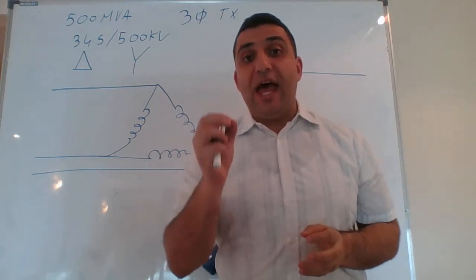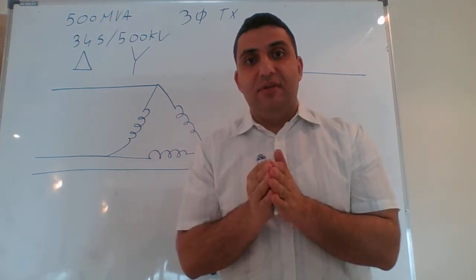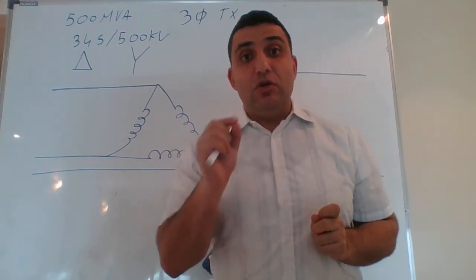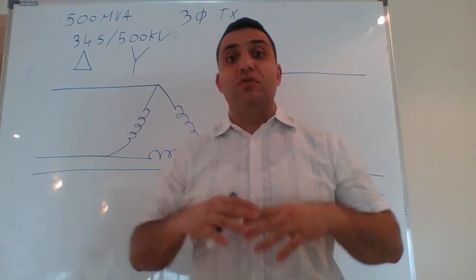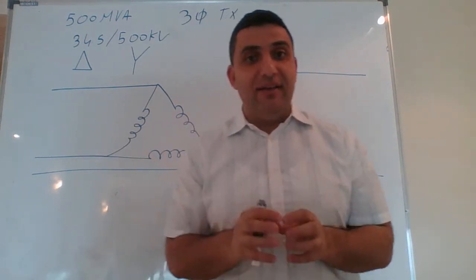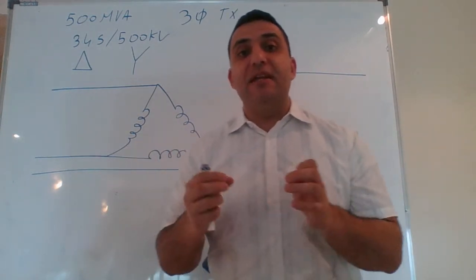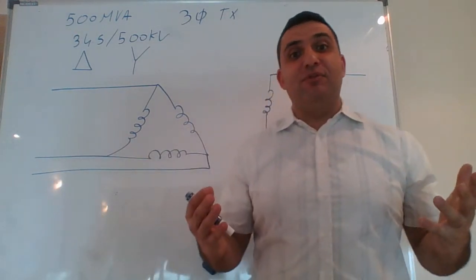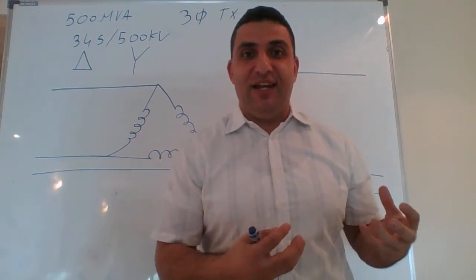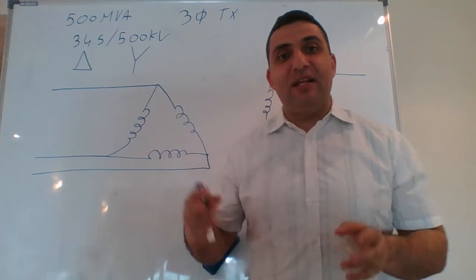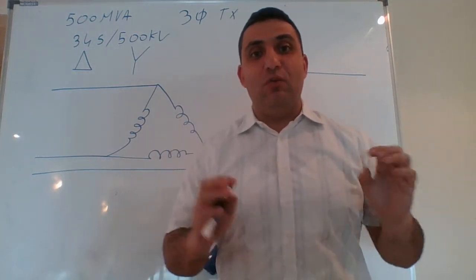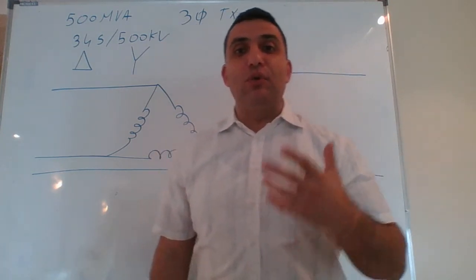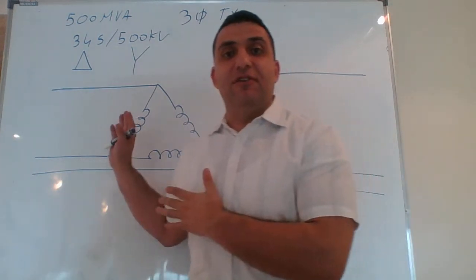This magnetizing inrush only happens on the primary side, not on the secondary side. Engineers noticed that the inrush current is made almost fully of harmonics, while the fault current is made almost purely from fundamental frequency. That's why it is possible for us to design a harmonic restraint relay to avoid tripping our differential relay under inrush current, which would be a false trip.